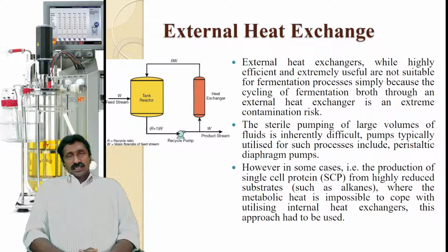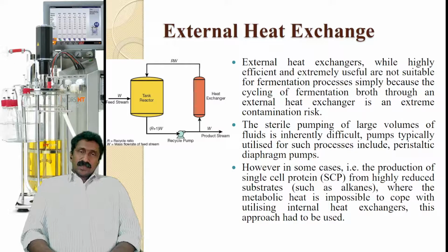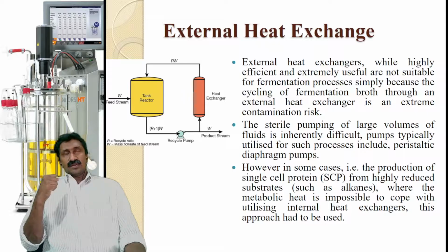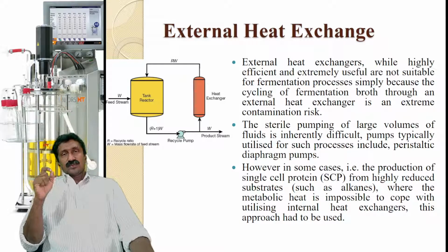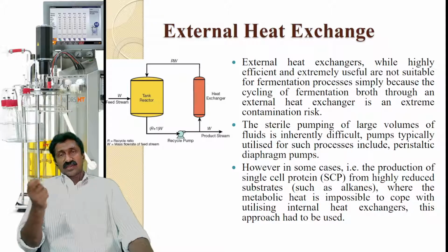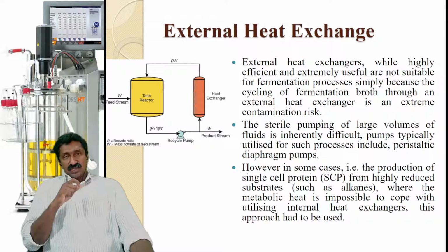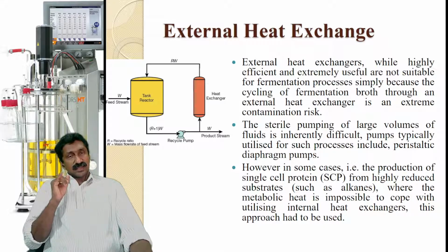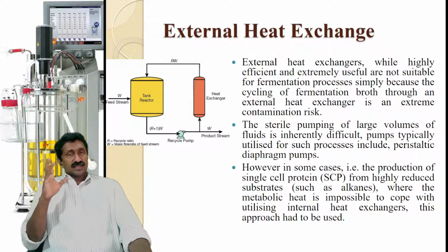So the next one is the external heat exchanger. The external heat exchangers, while highly efficient and extremely useful, are not suitable for the fermentation process simply because cycling the fermentation broth through an external heat exchanger is an extreme contamination risk. So usually it is not advisable unless it is really required. Otherwise, as I mentioned, normal bioreactor systems were designed with the previous two items, like jacket systems and internal pipes.